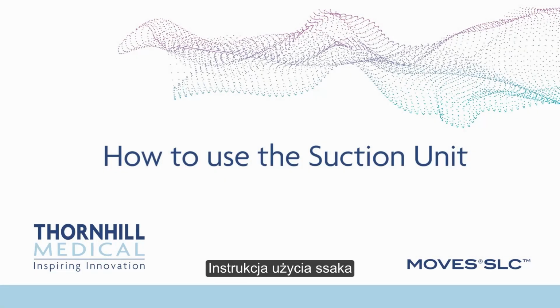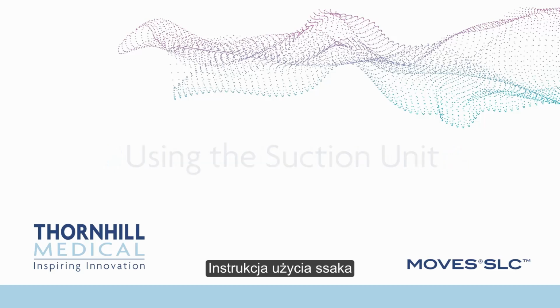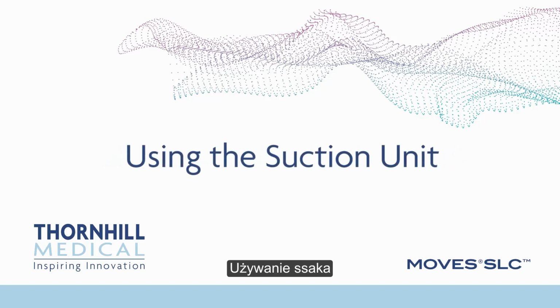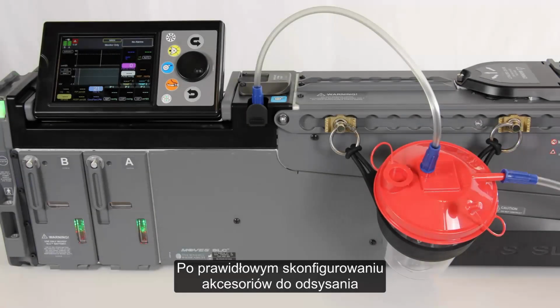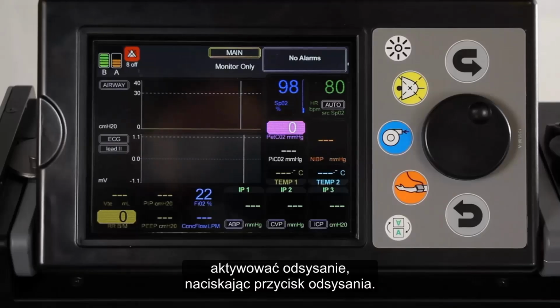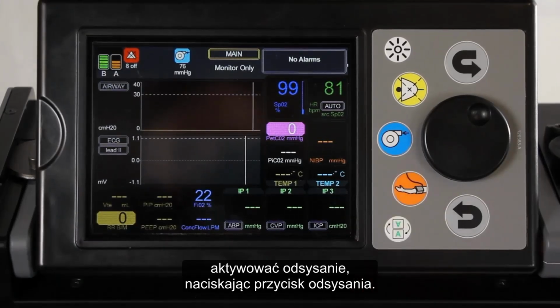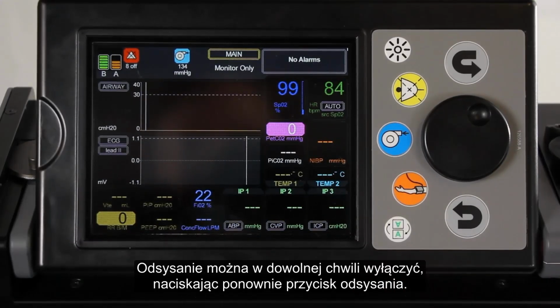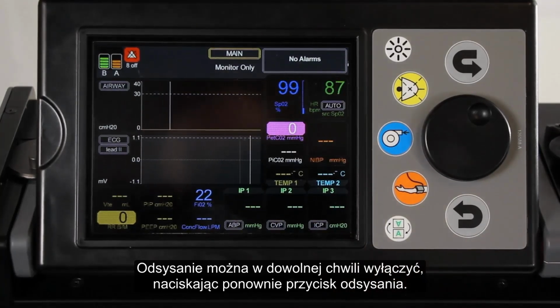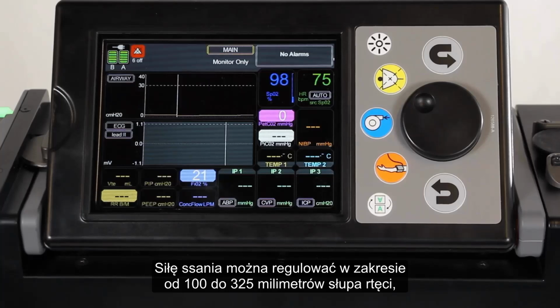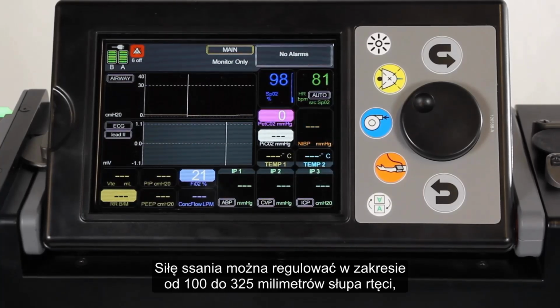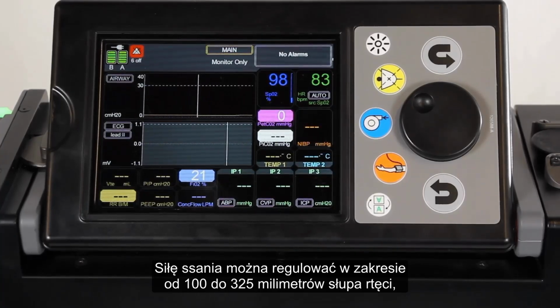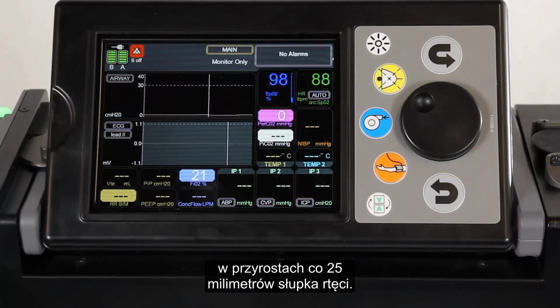How to use the suction unit. Using the suction unit. Once the suction accessories are set up properly, activate the suction by pressing the suction control button. Deactivate the suction at any time by pressing the suction control button a second time. You can adjust suction pressure between 100 and 325 millimeters of mercury in increments of 25 millimeters of mercury.